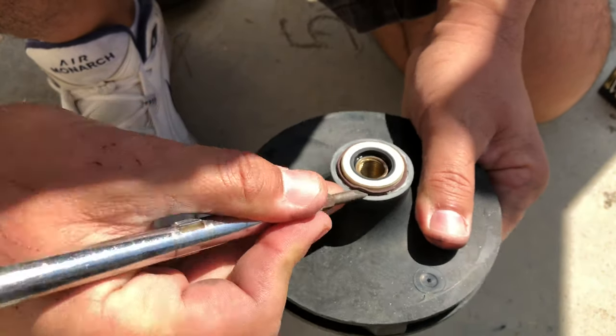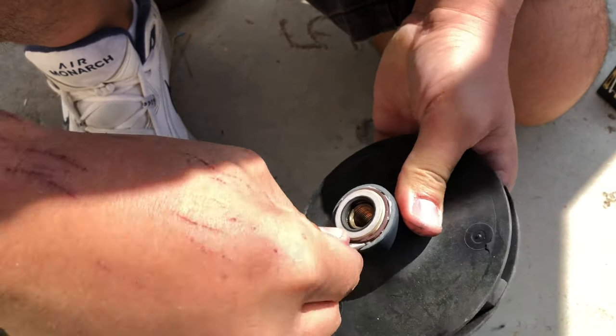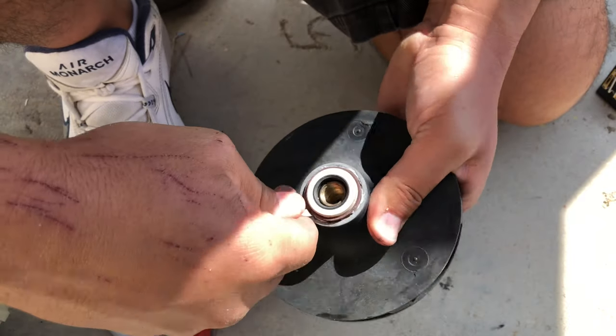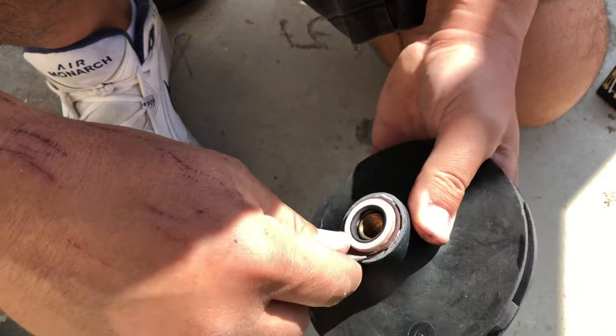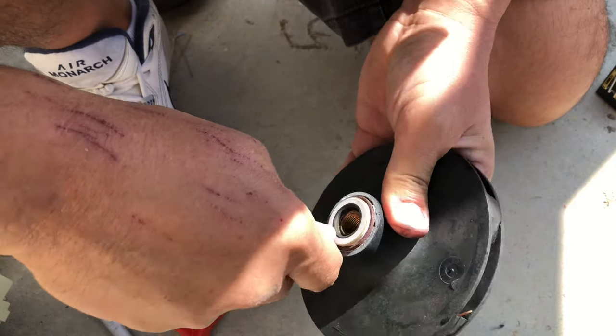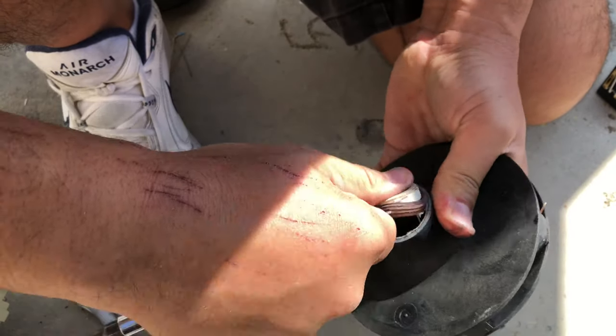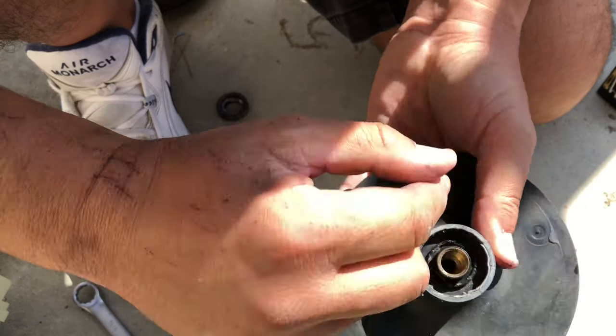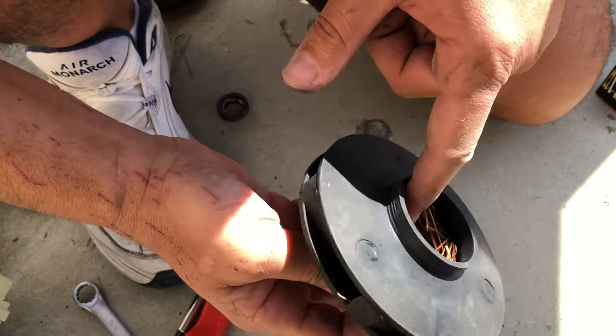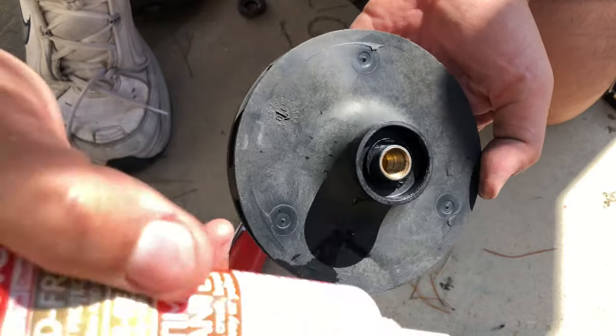To replace the other side, we have to pry the old ceramic seal out without wrecking the impeller — it's not easy. Once it's out, clean up the old silicone and clean out all the debris embedded in the impeller, which has really been slowing the pump down.